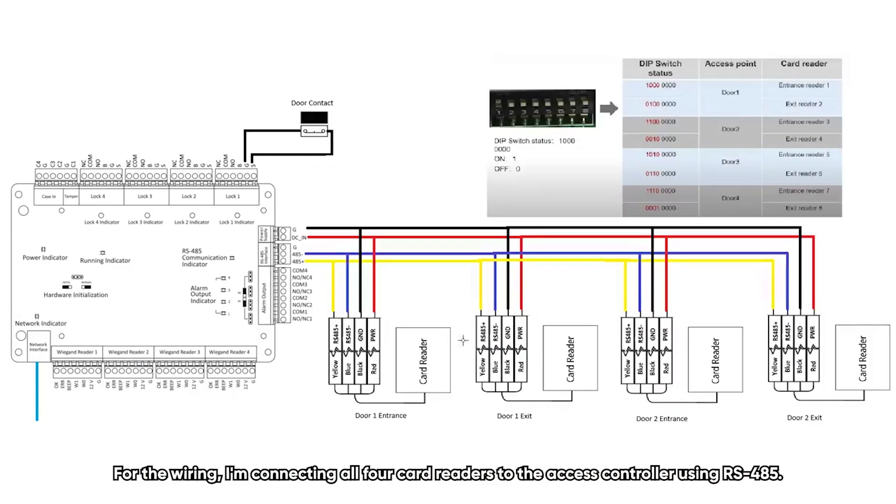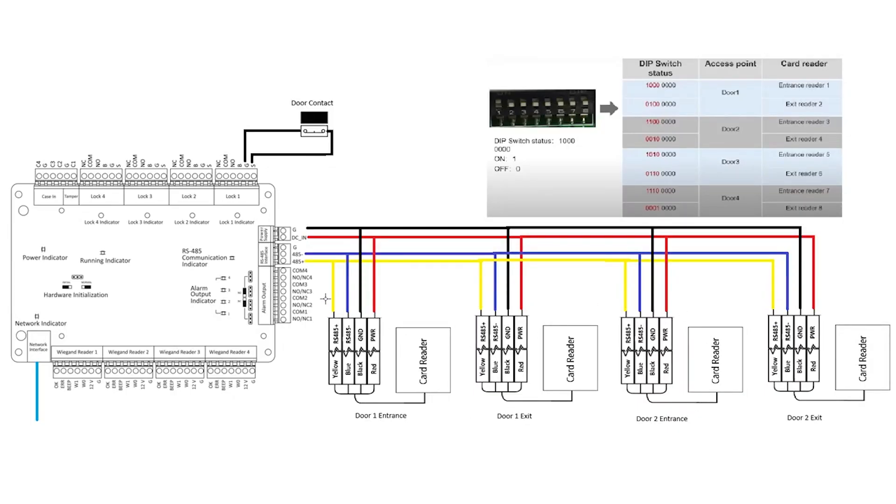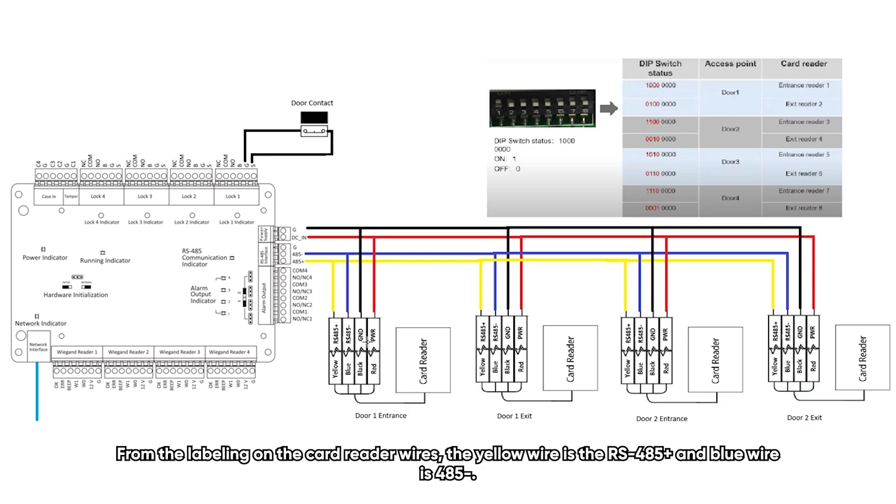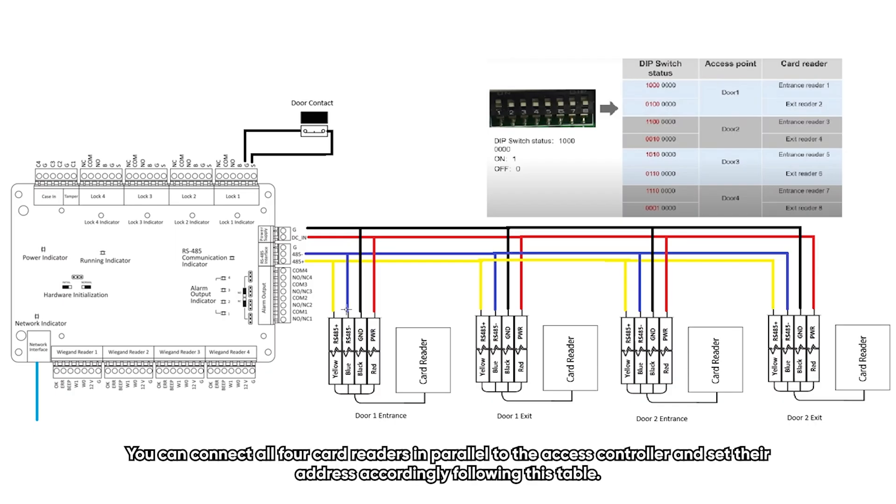For the wiring, I'm connecting all four card readers to the access controller using RS485. From the labeling on the card reader wires, the yellow wire is RS485 plus and blue wire is RS485 minus.